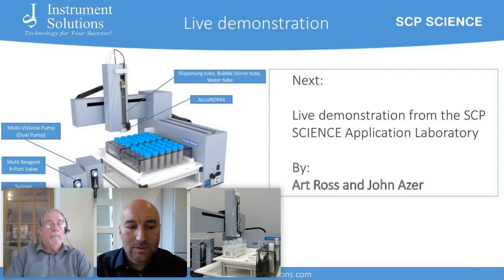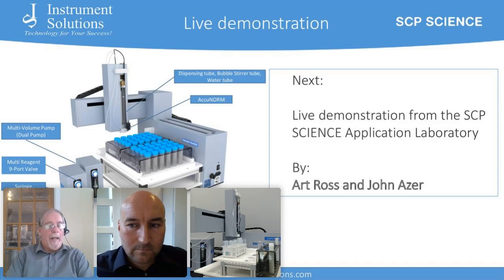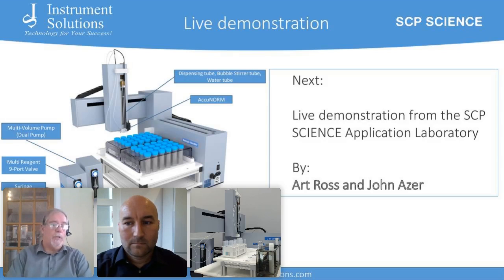May I add some things to this, Yaron? Of course. So the bulking pump uses a membrane pump. It only uses one diluent. It's fine to work with an acid solution, if you wanted to add a 1% nitric acid solution, it's fine to use it with an acidic solution. The bulking pump typically runs at about 13 mLs per second. The rule of thumb is that if you add 8 mLs of acid to do your digestion on a resistive block, you're going to have less than 8 mLs when the digestion is done. So if you're normalizing to 50, you would take 50 milliliters minus 8, and that's the volume that you would add with the bulking pump, and then the normalization can be used to normalize with precision to the 50 milliliters. The precision of the bulking pump is about 1% in terms of the volume that you're asking for.